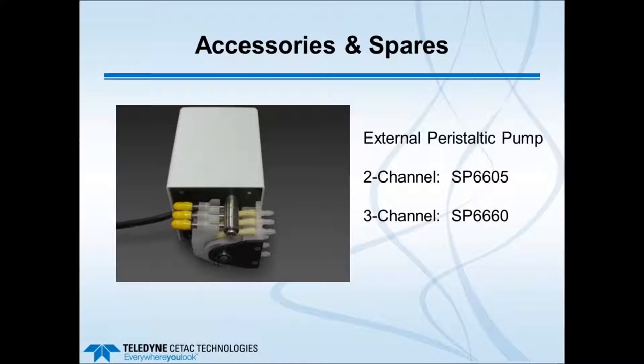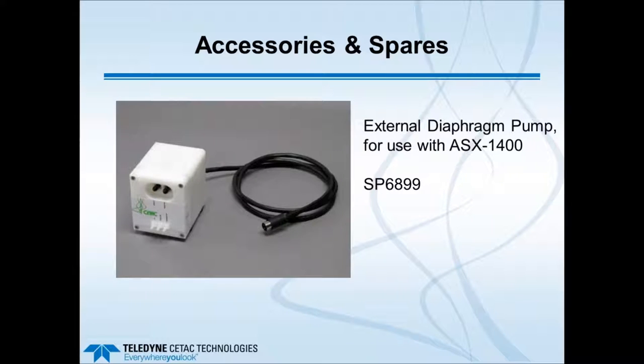There is an optional external peristaltic pump available if your auto sampler does not have a built-in peristaltic pump to fill the rinse station. This plugs into the electronic control module of the ASX Express and is available in two-channel and three-channel options, though it is not standard with the ASX Express. There is also an optional external diaphragm pump for moving oils such as kerosene or Premisolv to the rinse station of an ASX 1400 or 1600 auto sampler, also connecting to the back of the electronic control module.